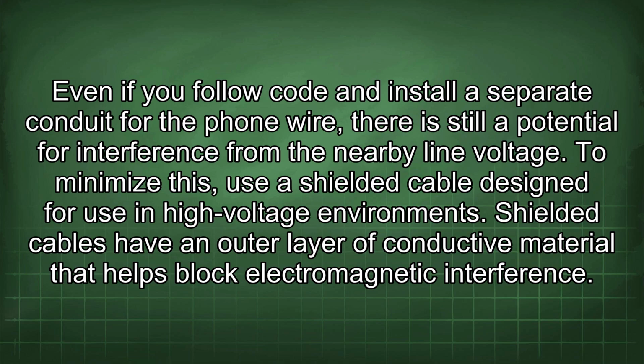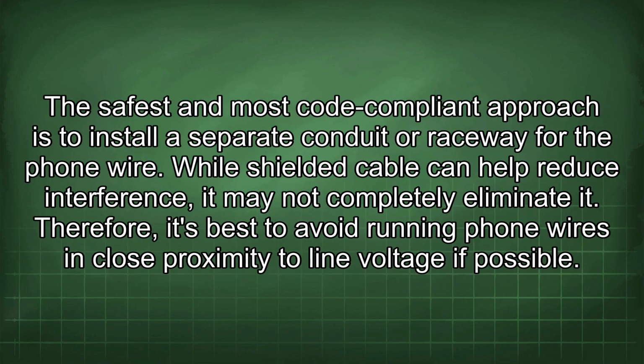To minimize this, use a shielded cable designed for use in high-voltage environments. Shielded cables have an outer layer of conductive material that helps block electromagnetic interference. The safest and most code-compliant approach is to install a separate conduit or raceway for the phone wire. While shielded cable can help reduce interference, it may not completely eliminate it. Therefore, it's best to avoid running phone wires in close proximity to line voltage if possible.